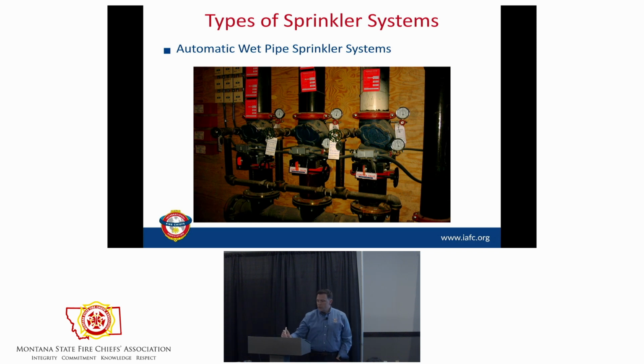3 risers, okay? So within every single riser system, this is your everyday big box, right? We want a riser to only cover so many square feet. So the codes say, hey, look, you can cover 40,000 in storage occupancies per riser, and the rest it's 52,000 square feet. So this riser right here, this is a riser, this is a riser. What is this thing? I have a standpipe. Anybody want to counter? What's a key component of a sprinkler system that we care about? Okay, it could be water. Yeah? This is the FDC pipe. I just happen to know because I took the picture.